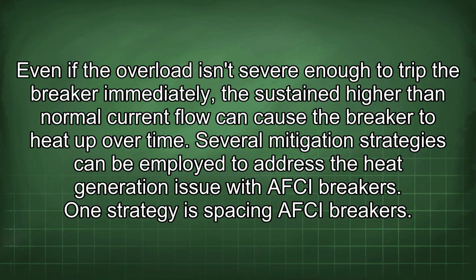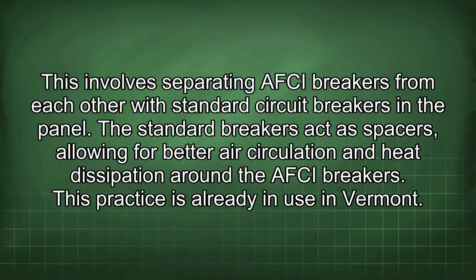Several mitigation strategies can be employed to address the heat generation issue with AFCI breakers. One strategy is spacing AFCI breakers. This involves separating AFCI breakers from each other with standard circuit breakers in the panel. The standard breakers act as spacers, allowing for better air circulation and heat dissipation around the AFCI breakers. This practice is already in use in Vermont.